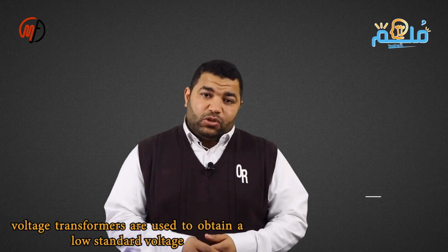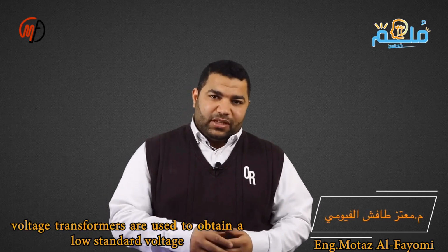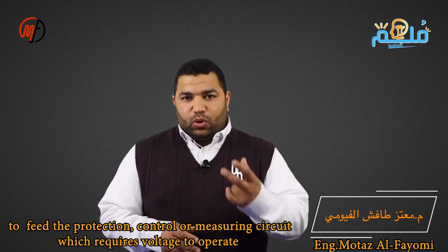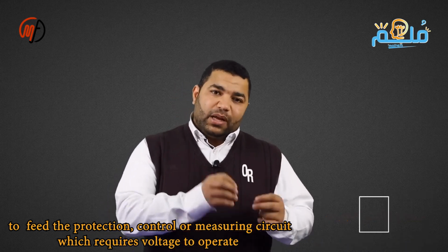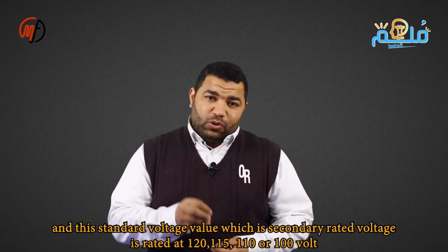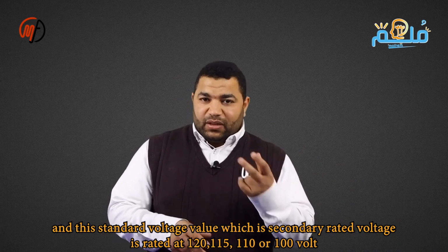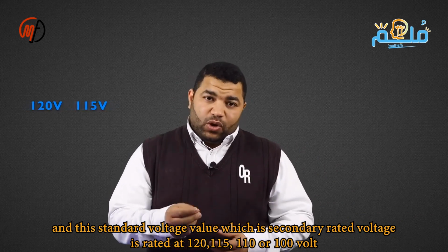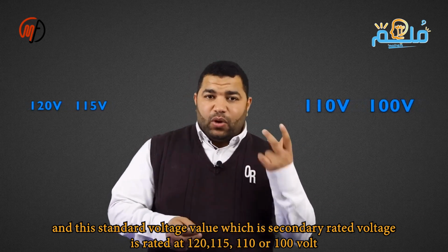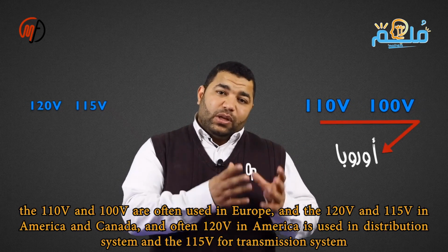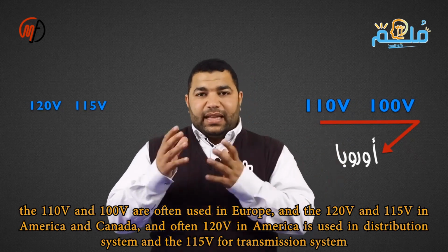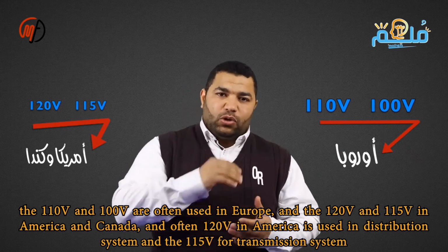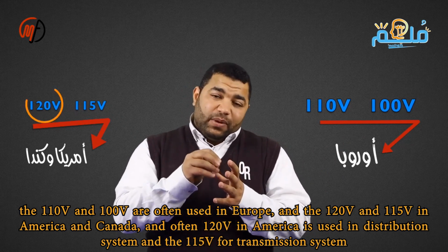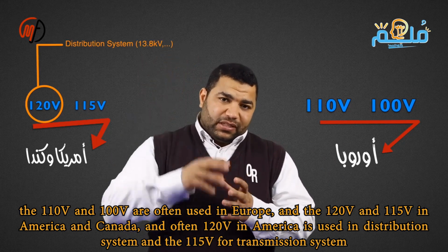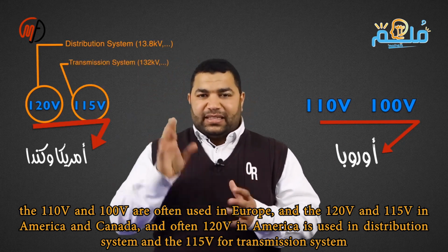Voltage transformers are used to obtain a low standard voltage to supply protection, measurement, or control circuits that require voltage to operate. This standard value for the voltage transformer, known as rated voltage secondary, is either 120, 115, 110, or 100. Typically, 110 or 100 is used in Europe, while 120 or 115 is used in the United States and Canada. In the US and Canada, 120 is commonly used in the distribution system, and 115 is used in the transmission system.